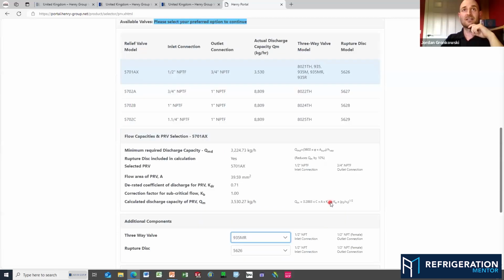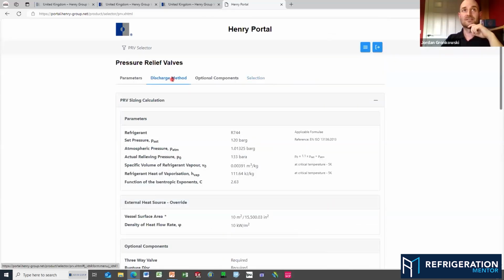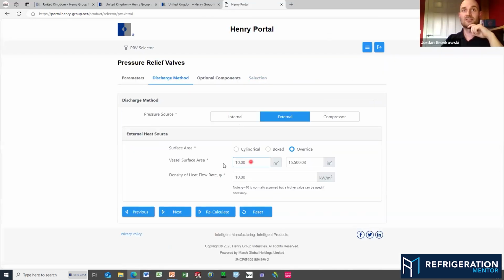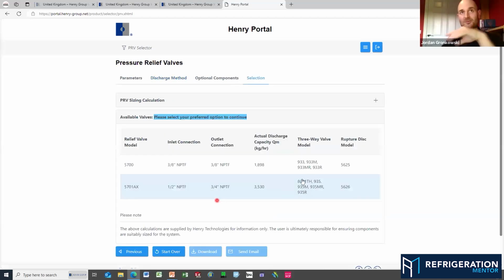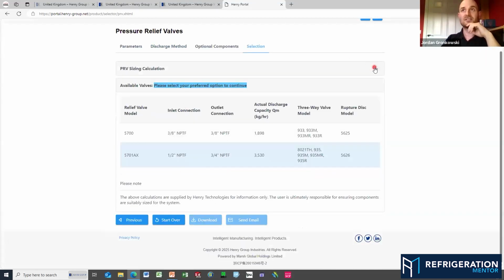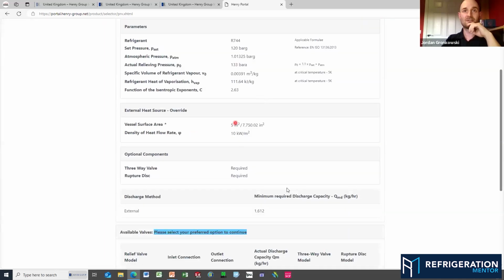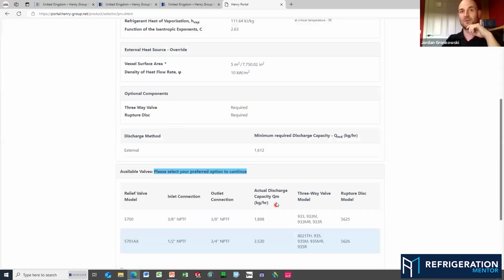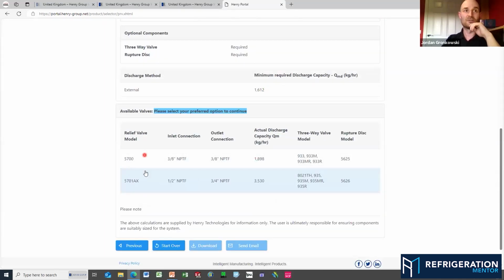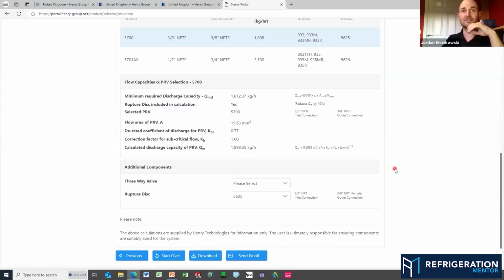You can go back by clicking and deciding you want to change something. So say you've got, oh, I made a mistake there, it's supposed to be 5. You can recalculate. You can jump straight to the end again. Now you can see, because we've reduced the surface area, our requirement is now 1,612 because it's half the surface area. So we've got two different valves. We've got the valve we selected last time, but we've also got the option of the smaller one now, which is 1898. Again, gives you the option to tick all that.